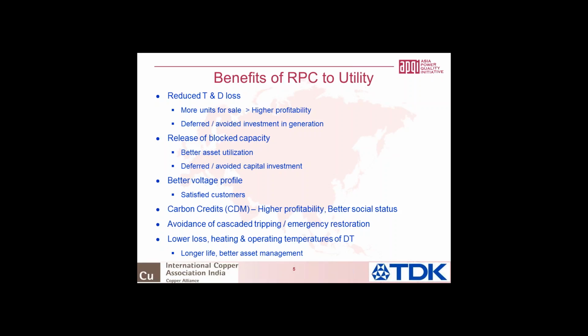You have a better voltage profile, which means more satisfied customers. Even a basic customer whose tube light doesn't come on will be very happy because his tube light does come on because he's got a better voltage profile. Of course, as I said, utilities can also go in for carbon credits, which means higher profitability. You can trade carbon certificates and also get better social status. In fact, some of these are under the corporate social responsibility umbrella. In some cases, you can even avoid a cascaded tripping. And reactive power management is one of the essential elements of emergency restoration, a key thing for the utility. And of course, when there are lower currents and lower losses, you have lower heating and lower operating temperature of the distribution transformers, which means a longer life and better asset management. This is well known, utilities would be much better off.